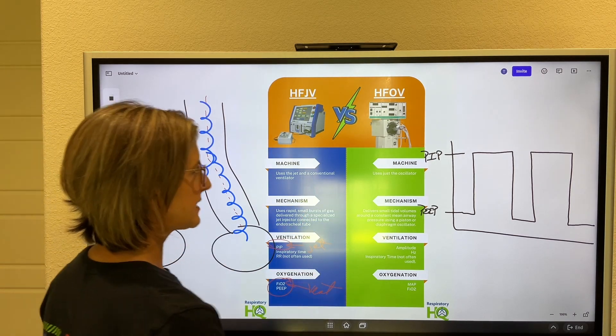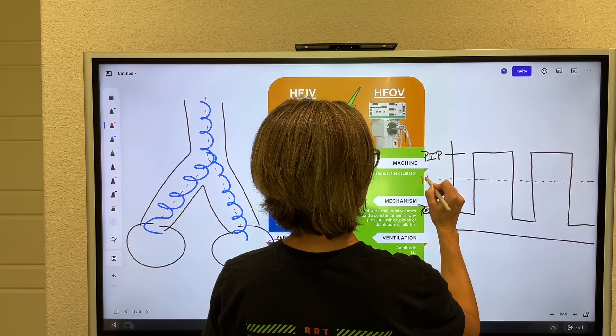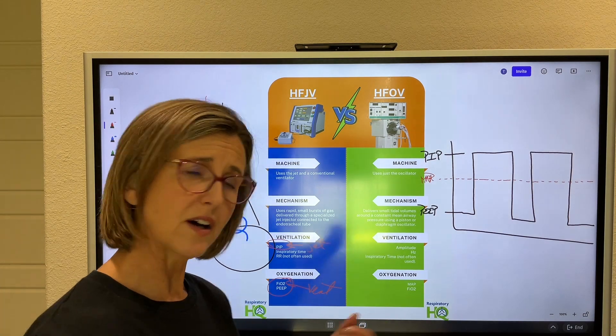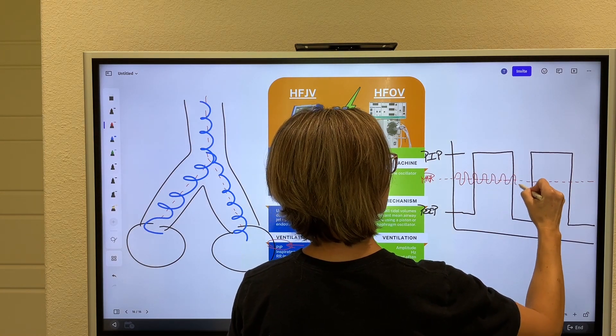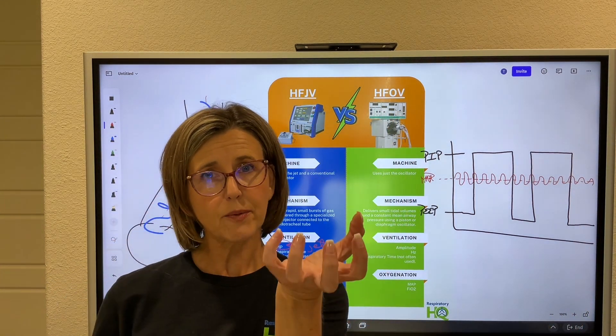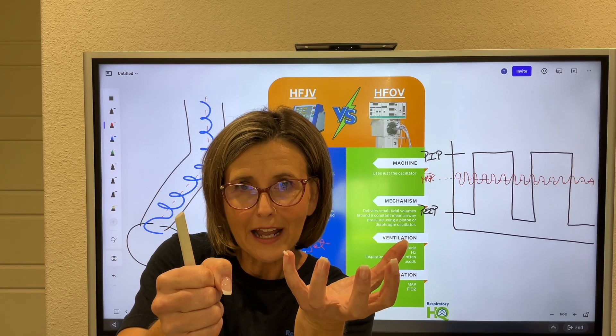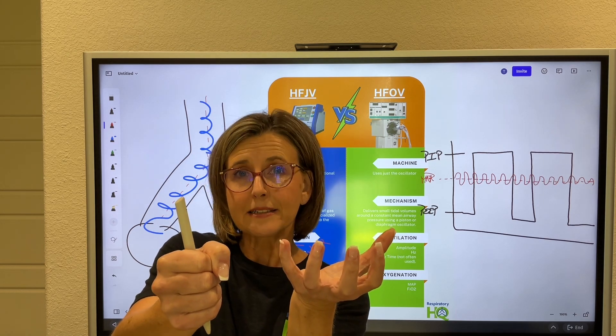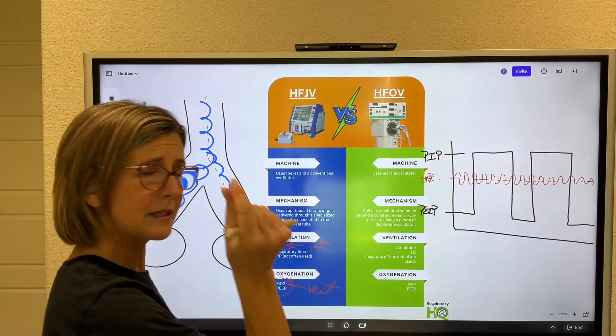With the oscillator, you set a mean airway pressure. A piston or diaphragm in the oscillator delivers very small tidal volumes around this mean airway pressure at a very fast rate. This is called an open form of ventilation — the mean airway pressure pops the alveoli open, then the piston pushes tidal volume in for inspiration and draws back for exhalation. So both inspiration and exhalation are active with the oscillator, cycling back and forth with super fast, itty-bitty small tidal volumes.